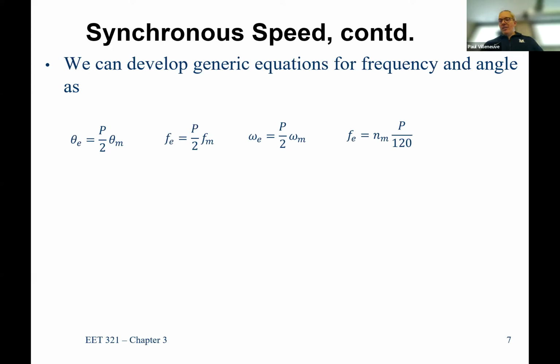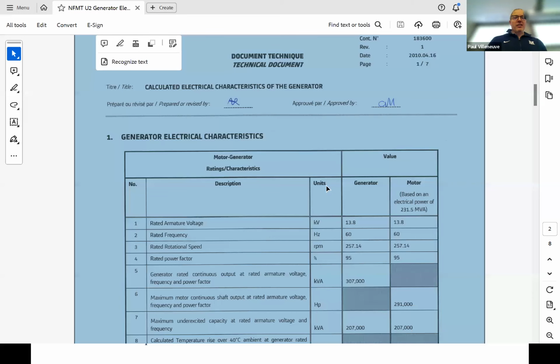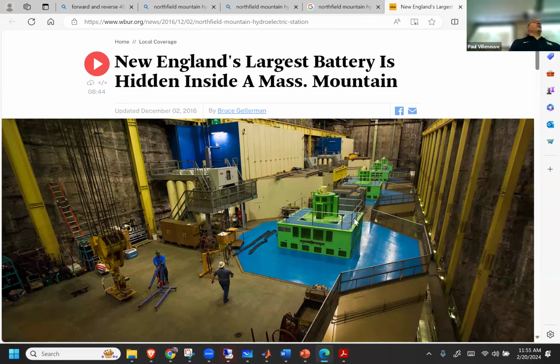Power equals torque times omega, so the more poles you have, the more torque you've got. Look at Northfield Mountain: those shafts are like 2 feet in diameter because there's a lot of torque, really working hard to spin. Whereas a 300 megawatt generator spinning at 3,600 RPM might only be 6 to 8 inches, much smaller. More poles means more torque and less speed.